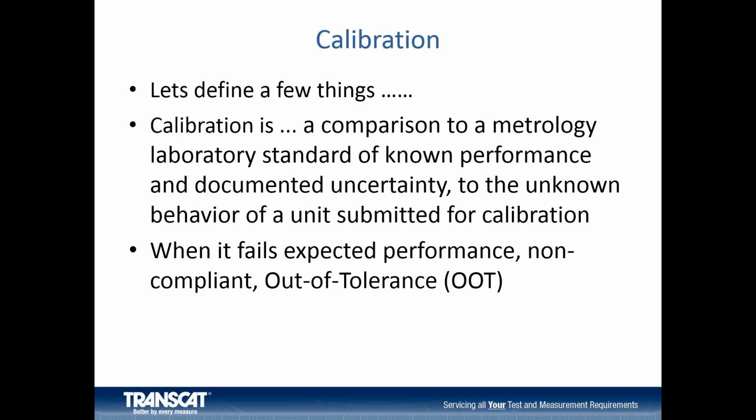Let's define a few things before we get going. Believe it or not, us metrologists have our own dictionary. We call it the Vocabulary of International Metrology, the VIM. It has a full page-long definition for calibration, but I'm just going to pare that down to something realistic here. So basically, calibration is a comparison to a metrology laboratory standard of known performance and uncertainty to the unknown behavior of a unit submitted for calibration.